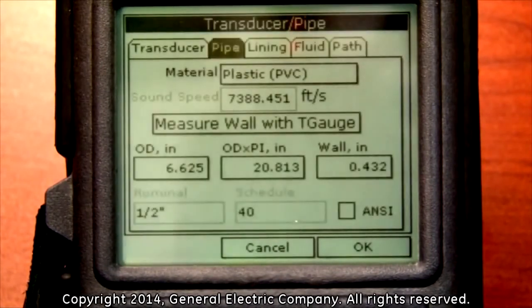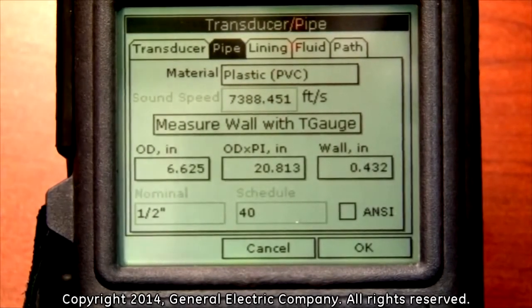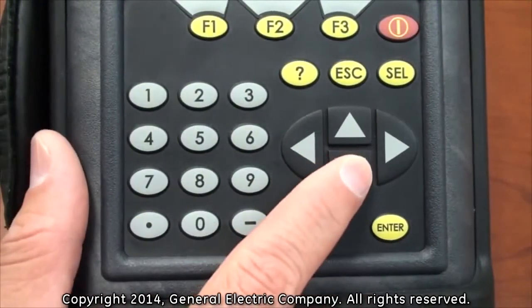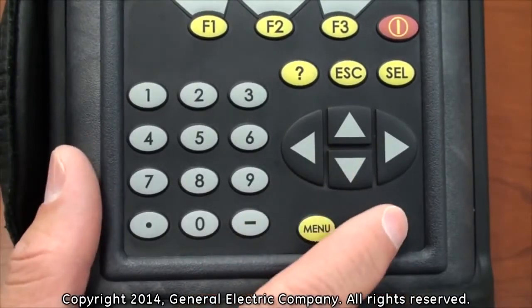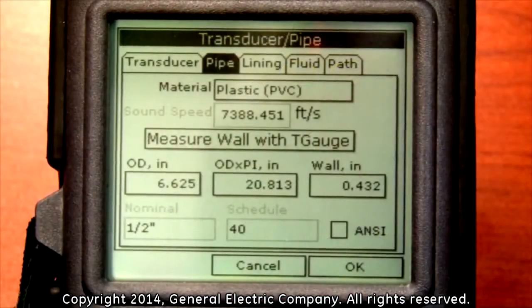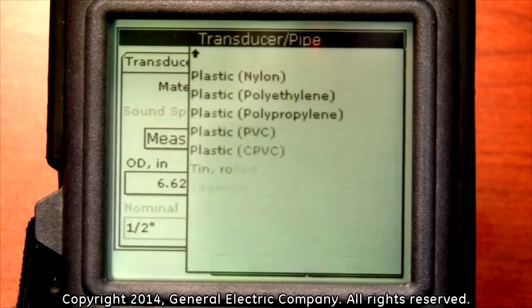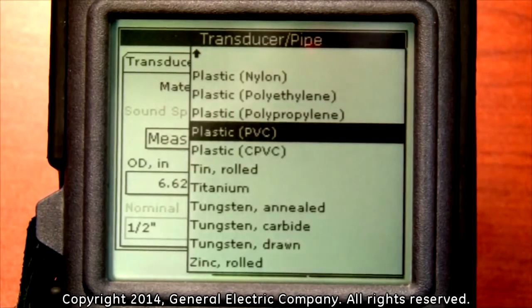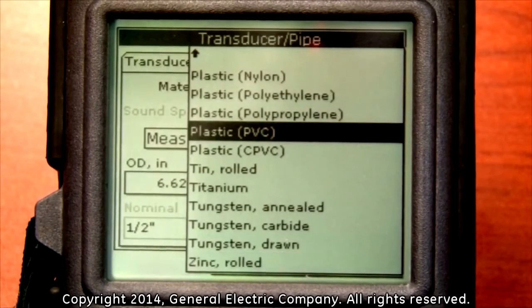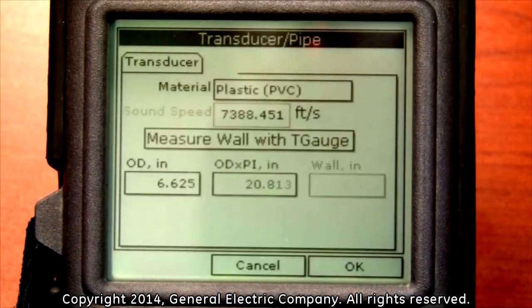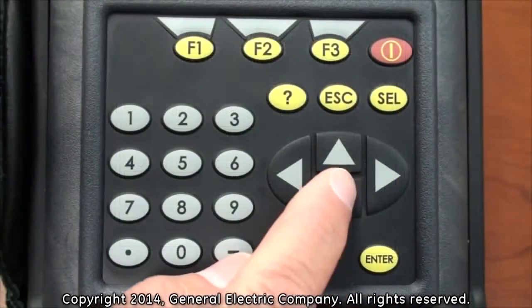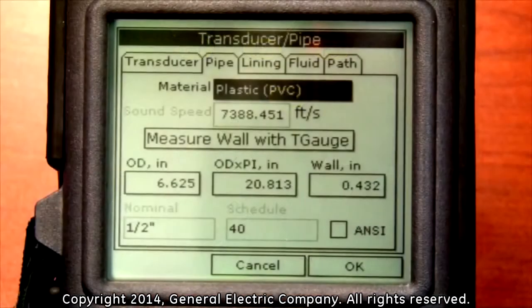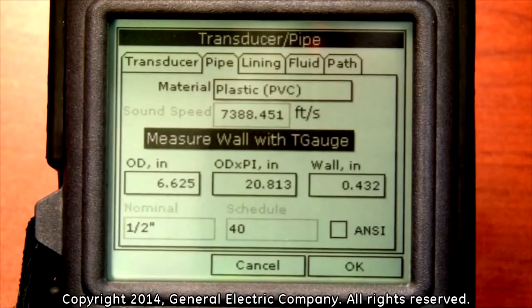In this menu, you can select the material and wall thickness of the pipe. Press the down arrow key to highlight the material input field and press the Enter button to view the available material types. You can use the up and down arrow keys to navigate through the pipe materials. Once you have selected your pipe material, press Enter. The next option to program is the wall thickness. This will be covered in another video segment devoted entirely to measuring wall thickness.